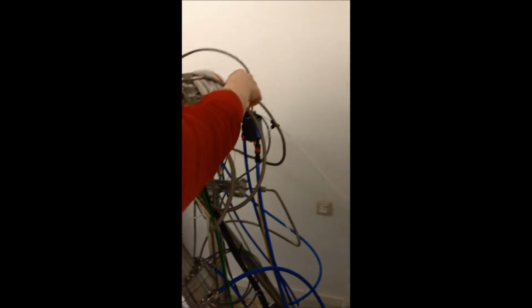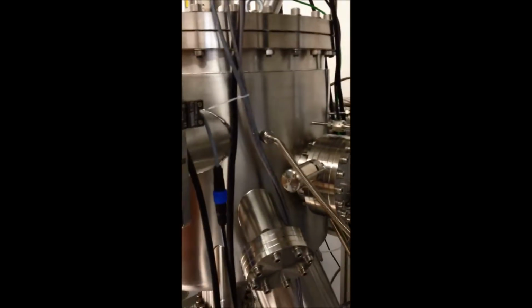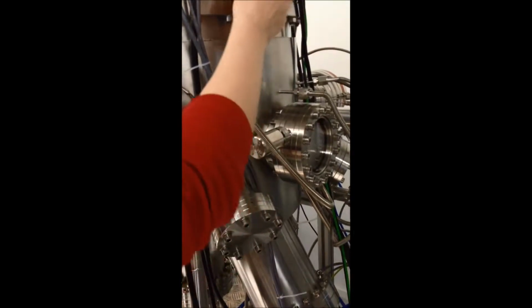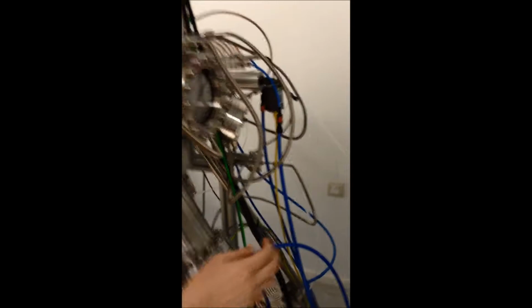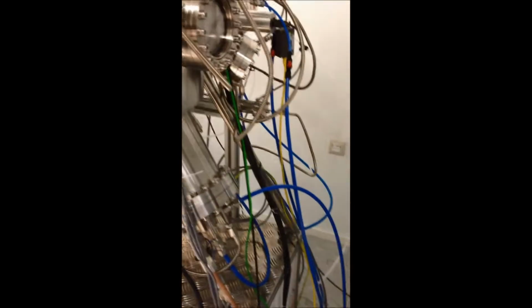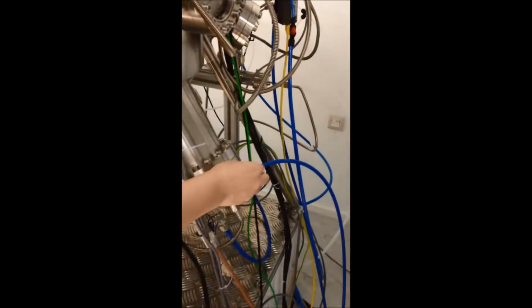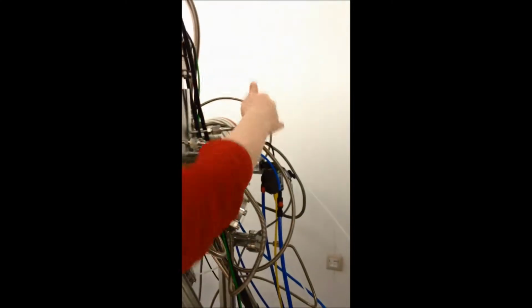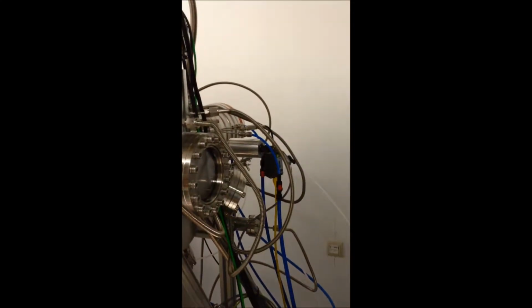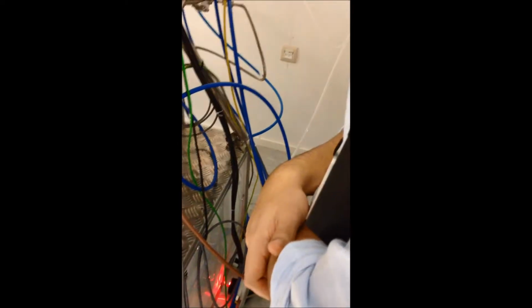The other line is the QCM turbo. The one that should heat more is this one, right? It will get quite hot when the heater is going. Yeah, it gets very hot. So just make sure if you do disconnect any of the water lines, make sure the QCM is disconnected first. The flow meters are always last, after everything.